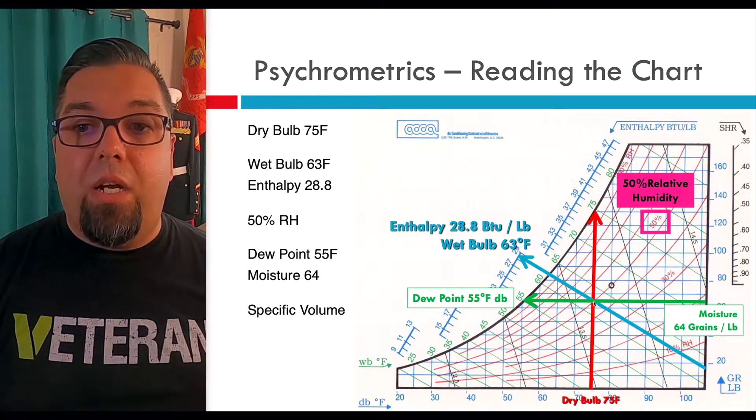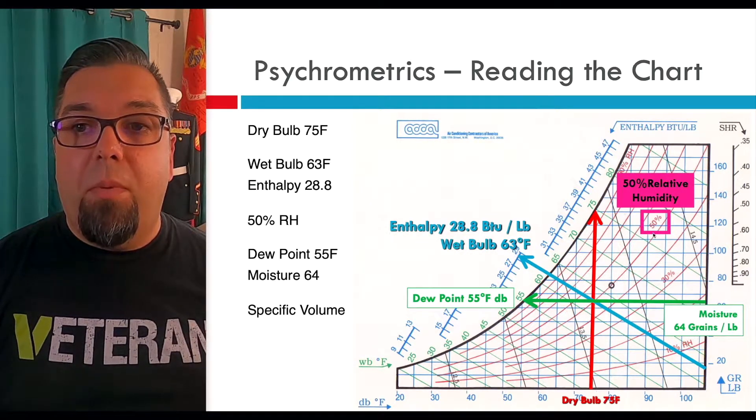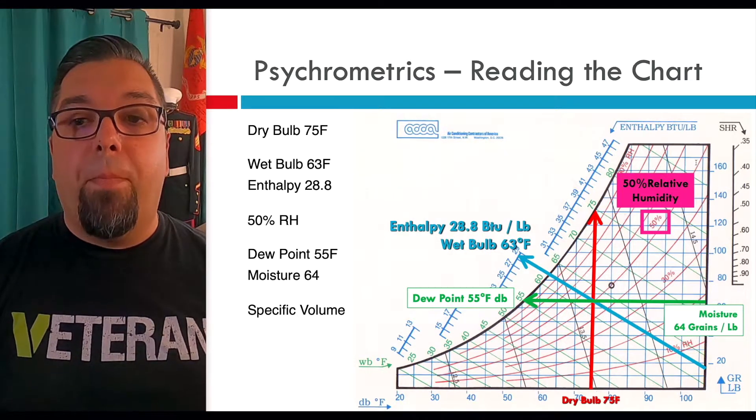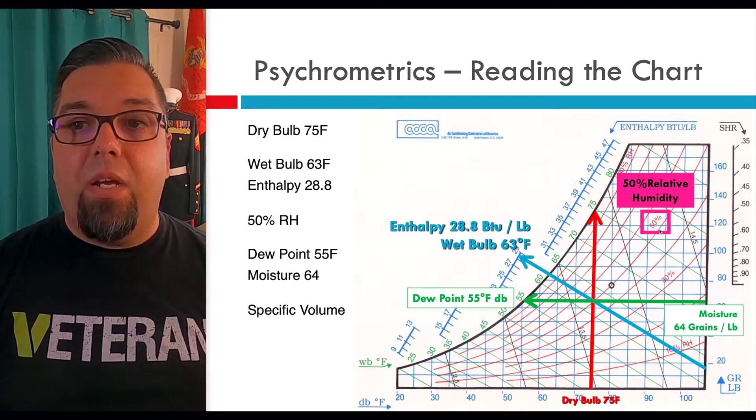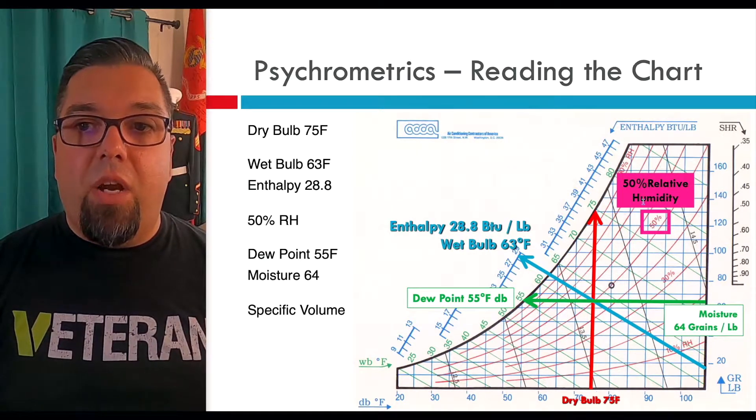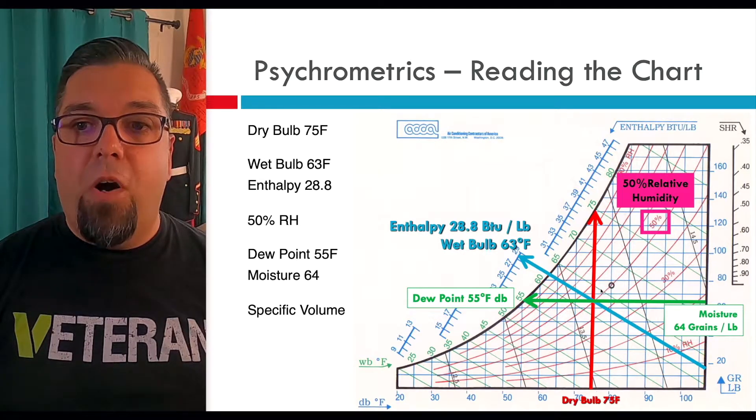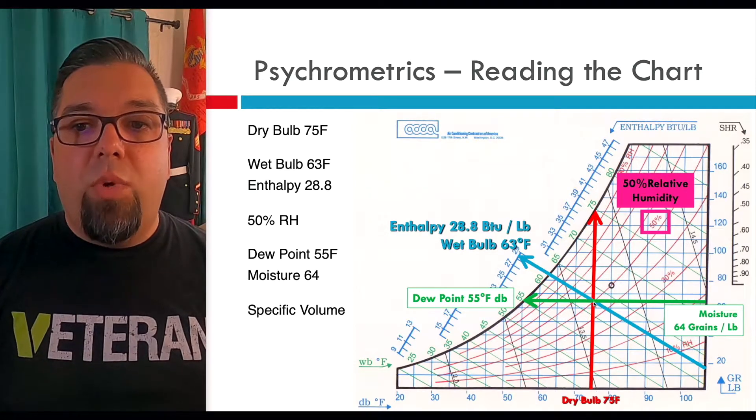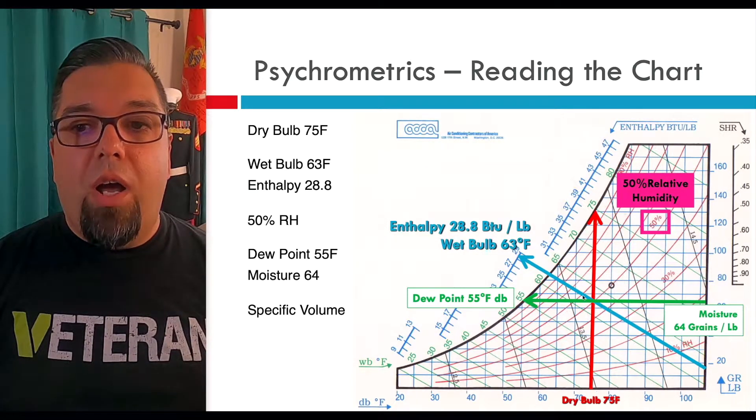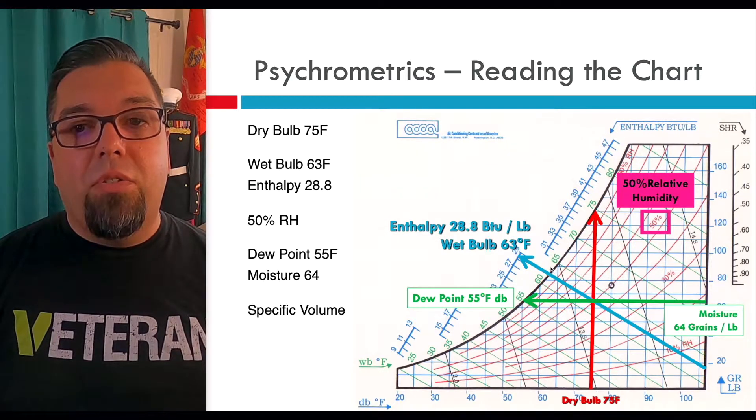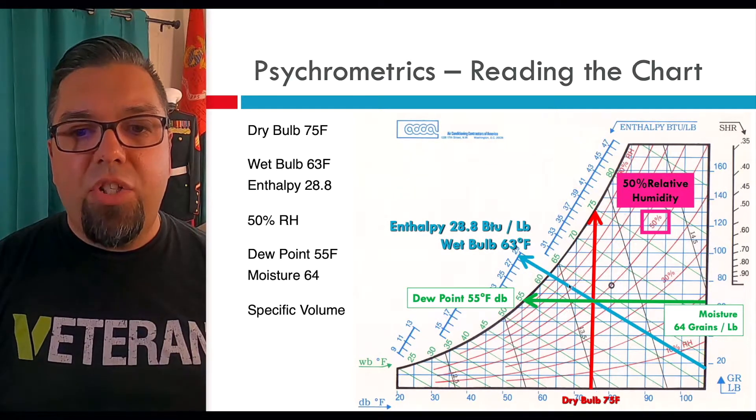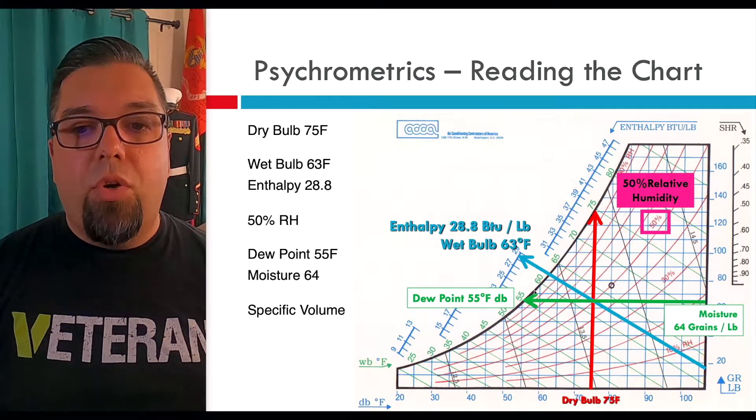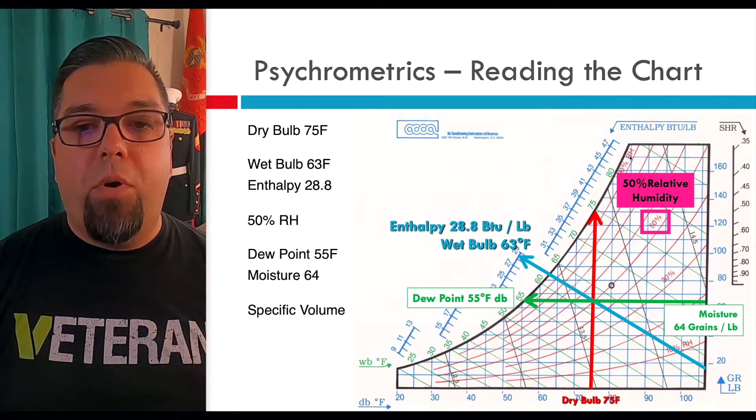As long as you have two pieces of information off the left hand side here you can plot and know everything else that's going on with the air off of the psychrometric chart. In this example I'm going to use our design temperature 75 dry bulb and 50% relative humidity and when I plot that point here right here on this 50% relative humidity, remember relative humidity are these curved lines that go from the bottom left to the top right and it's in pink or red. I blocked off the 50% line so you can see where it intersects our dry bulb at 75 degrees. If we draw a perpendicular line up you can see it's actually going to intersect with 63 wet bulb right here.